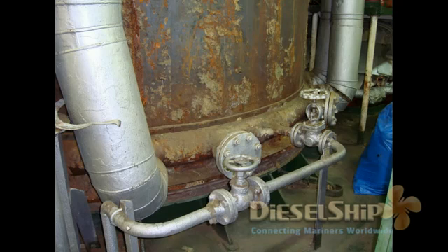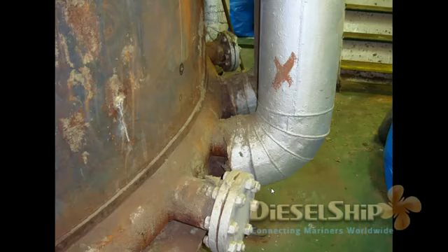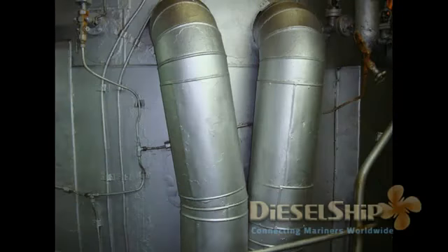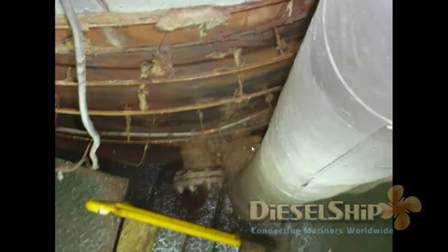And these are the blowdown valves. So we have two valves over here. These are the bottom blowdown valves. Let's see some more pictures. Yeah, so this is another view of a downcomer, completely insulated. One more picture, two downcomers which are huge in nature, just to maintain the ratio of 4:1. And just a top view from the top. See how big the downcomer is, connecting the water ring at the bottom.